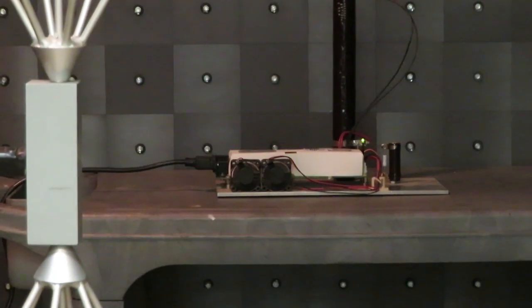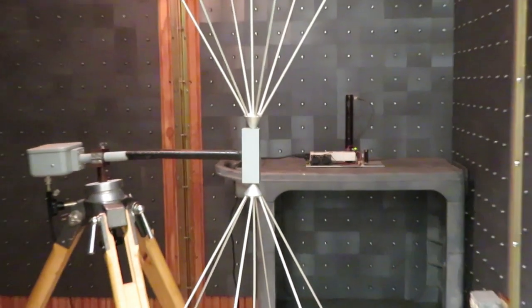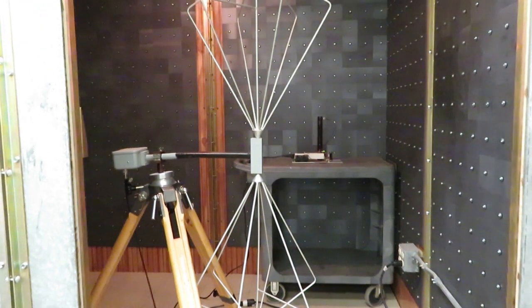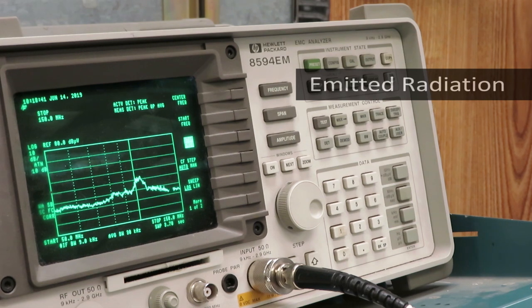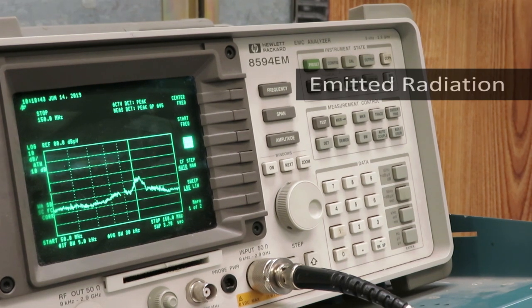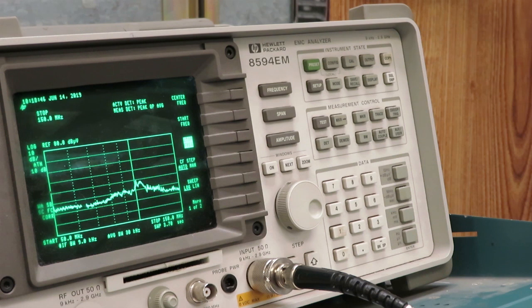It isolates the device under test from outside sources of radiation. The antenna will pick up any emitted radiation from the device. Connecting the antenna to a spectrum analyzer outside the chamber, we can see what frequencies the device is emitting and how strong they are.